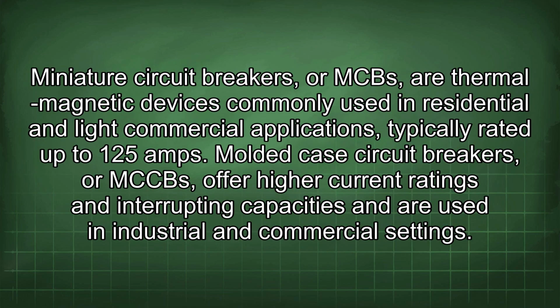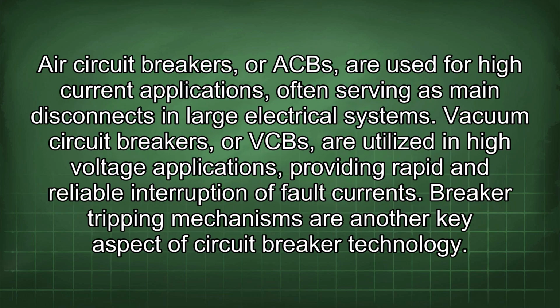Miniature circuit breakers, or MCBs, are thermal-magnetic devices commonly used in residential and light commercial applications, typically rated up to 125 amps. Molded case circuit breakers, or MCCBs, offer high current ratings and interrupting capacities and are used in industrial and commercial settings. Air circuit breakers, or ACBs, are used for high current applications, often serving as main disconnects in large electrical systems. Vacuum circuit breakers, or VCBs, are utilized in high voltage applications, providing rapid and reliable interruption of fault currents.